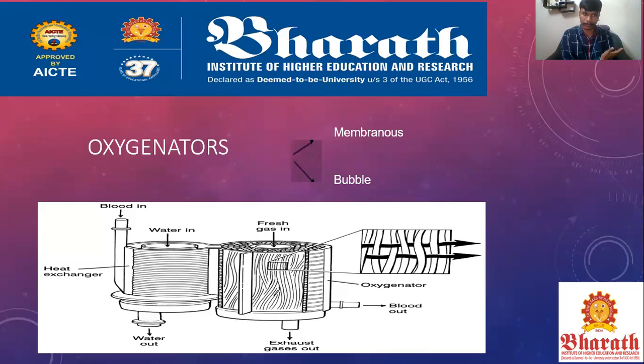It can be a centrifugal pump as well as a roller pump or impeller pump. Blood will be taken through the blood inlet tube and given to the heat exchanger, where the temperature will be maintained. Externally, water flow helps the blood maintain its temperature without coagulating or clotting. The heat exchanger is used to maintain the temperature of the blood.